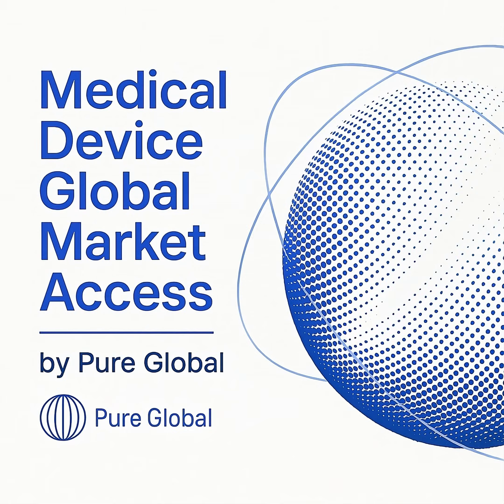Today we are discussing a significant update for manufacturers of hemodialysis devices. The US FDA's final guidance on pre-market notification, or 510(k) submissions for hemodialysis blood tubing sets. This document modernizes the agency's expectations, replacing a brief guidance that had been in place since 1984.